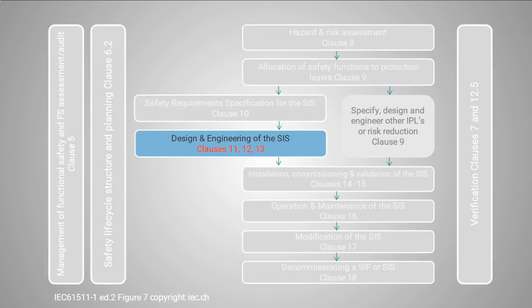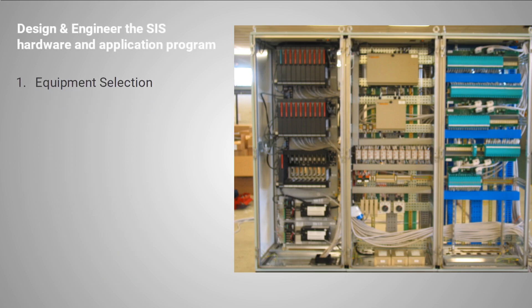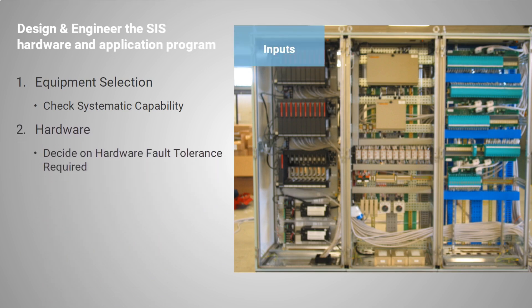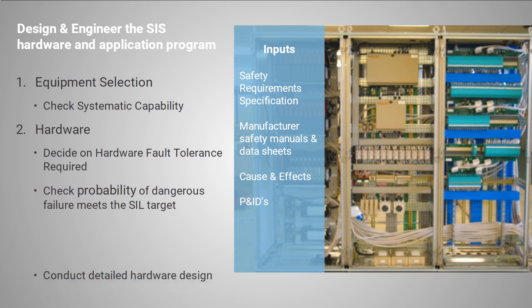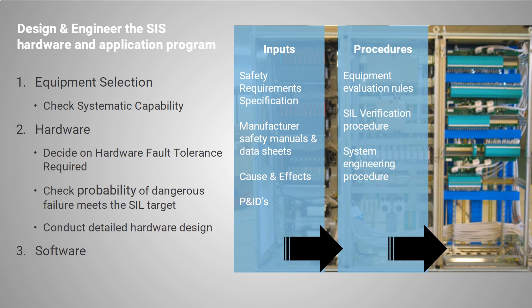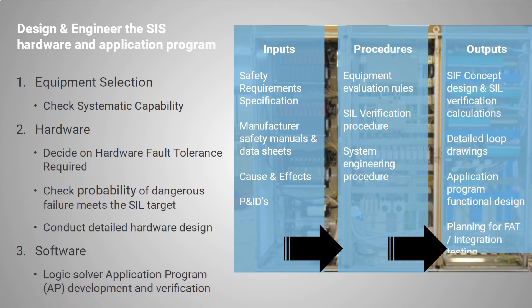When the requirements are sufficiently complete and stable, appropriate SIS equipment can be selected. Standards require this equipment to be specially assessed; usually this will involve ensuring only SIL-capable devices are used from reputable suppliers. Each safety instrument function will also need to meet special criteria for fault tolerance and have a calculation for probability of dangerous failure — something not required for a non-SIS control system. Logic solver application programs will also be developed in this stage, and verification by review and testing will be required to meet SIL targets.